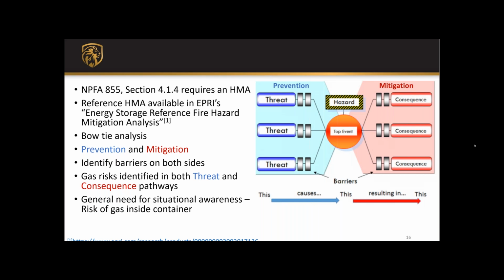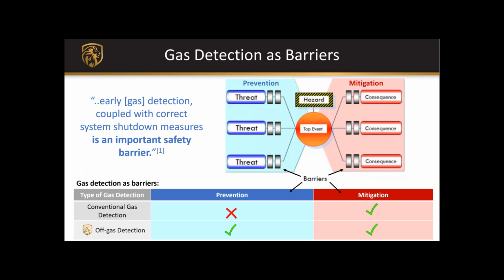Let's go to the next slide and look more specifically at using gas detection as barriers. The table at the bottom compares two types of gas detection: conventional gas detection, which I'd define as hydrogen or CO detectors, versus off-gas detection, which is the Li-ion Tamer system.